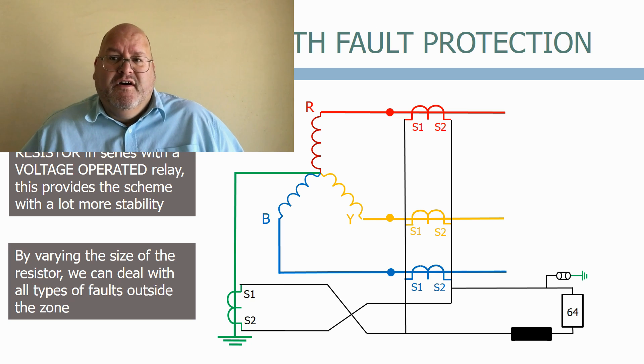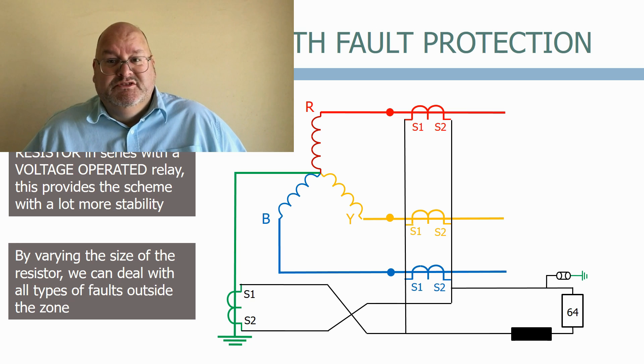Restricted earth fault protection is provided on most high voltage transformers, as it gives a clear indication that an earth fault has occurred on the winding being monitored. The stabilizing resistor value depends on the CT resistance and the resistance of the CT wiring. We will see how to calculate this in the future protection settings course. Thank you.